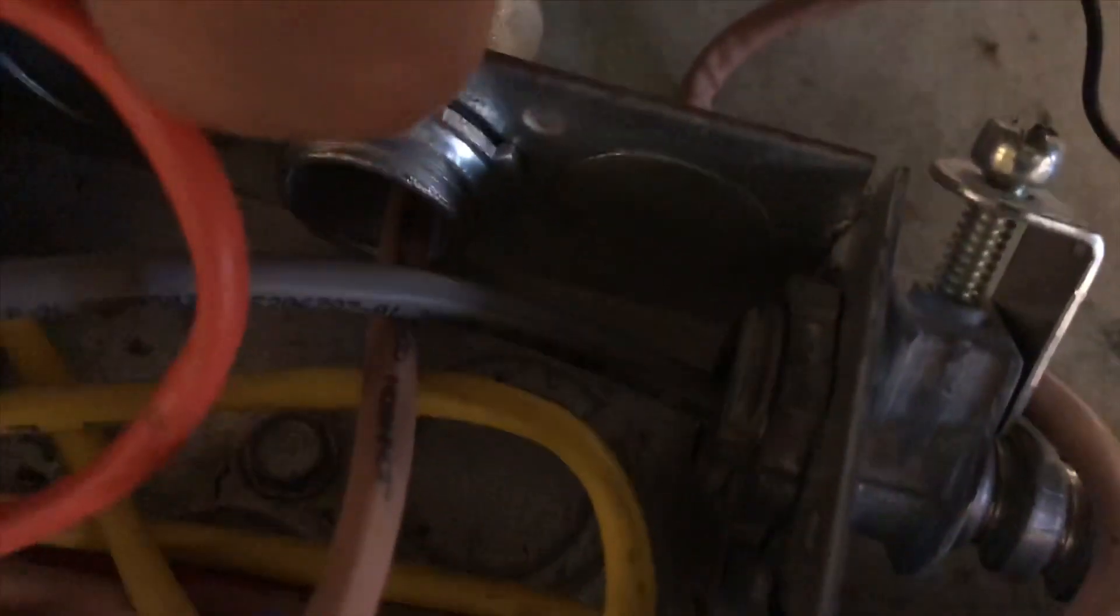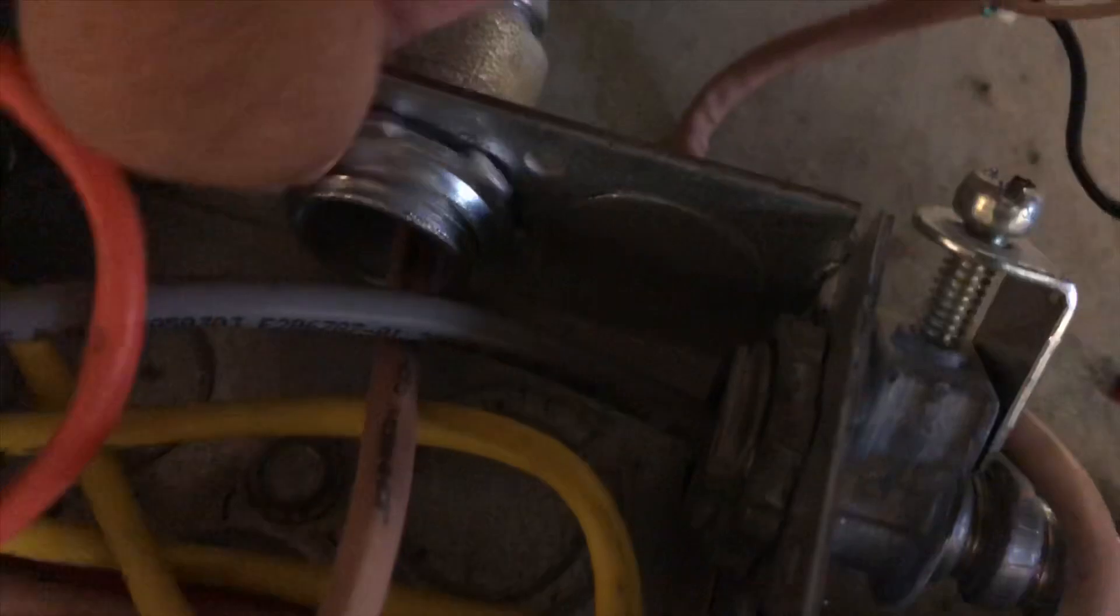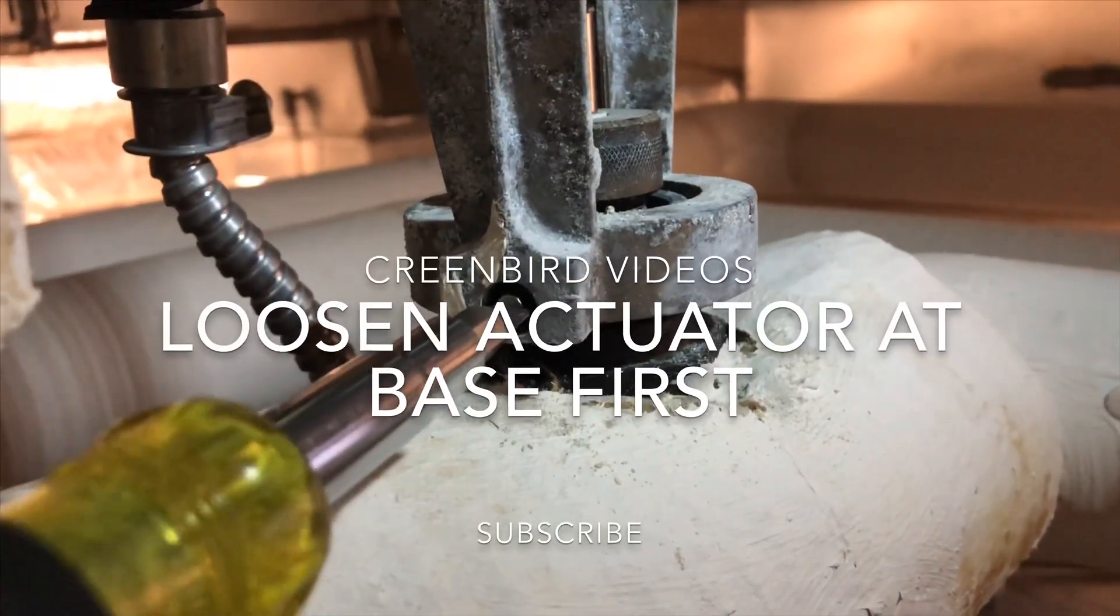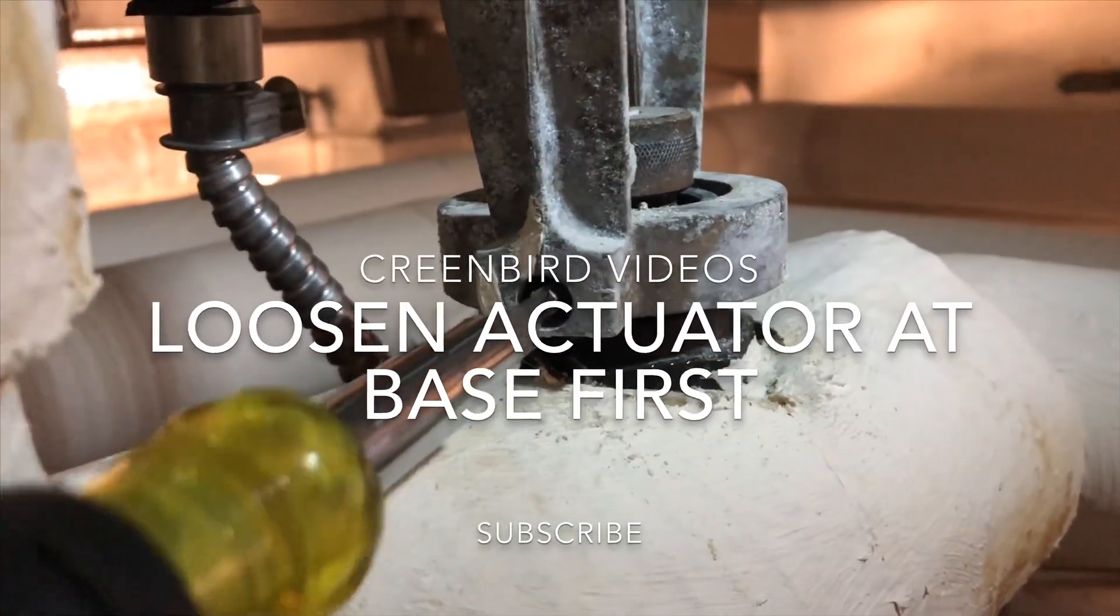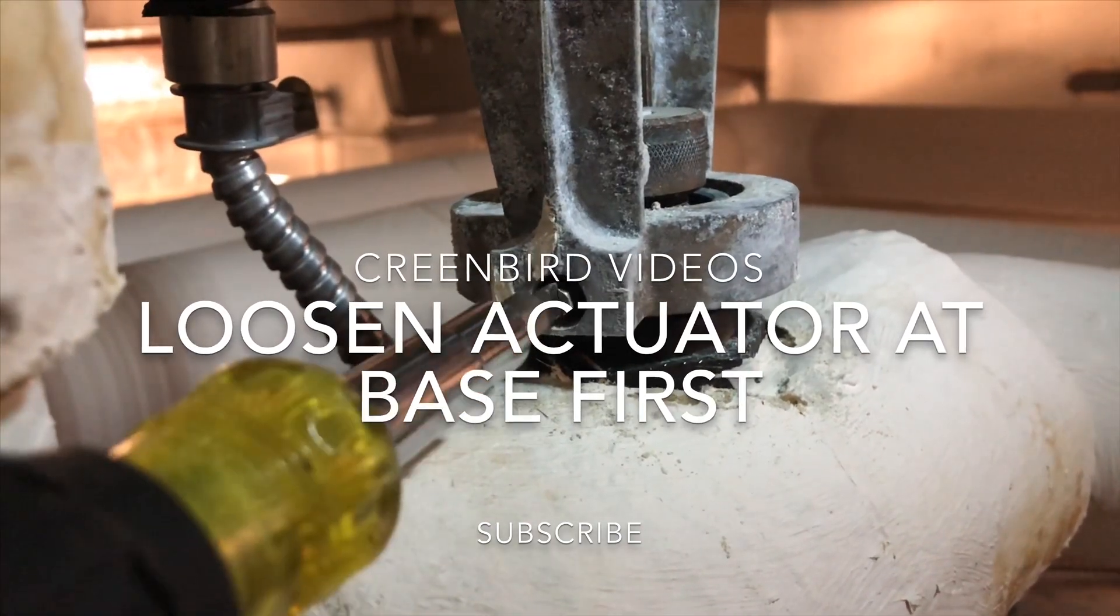Next, I'll unhook the armor flex going to the box because of where the location is of this actuator. I need to retrofit this to my new one. Next, I'm going to loosen the set screw that holds the old valve actuator to the valve.